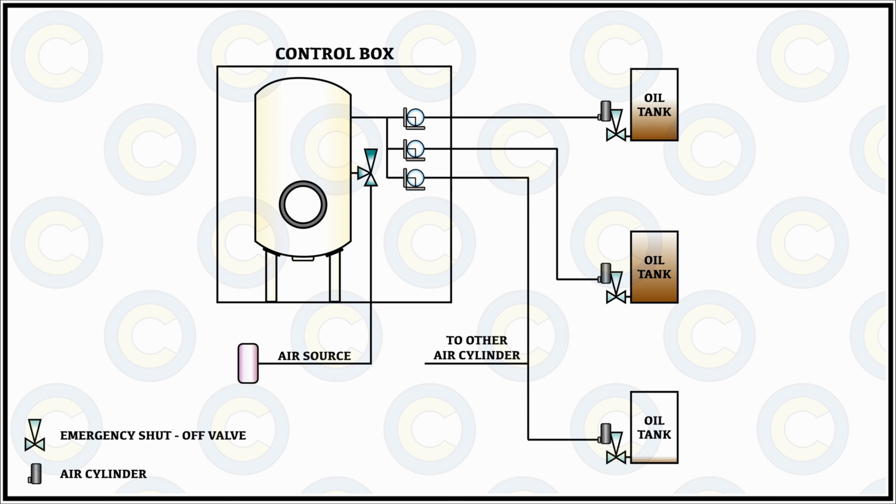Now let us imagine if something untoward was to happen with the compressed air system of your ship and we were not able to maintain the pressure within the reservoir, then what it would by default mean is that as the air pressure of this tank will keep going down, the valve would then lack the external force which was pushing it open and then get triggered and automatically shut, and that is something which we do not want to happen. So that is why, as a fail-safe design philosophy, the valve is kept open without the pressure of the air. The mechanism is designed in such a way, and it is the force of the air that closes the valve.